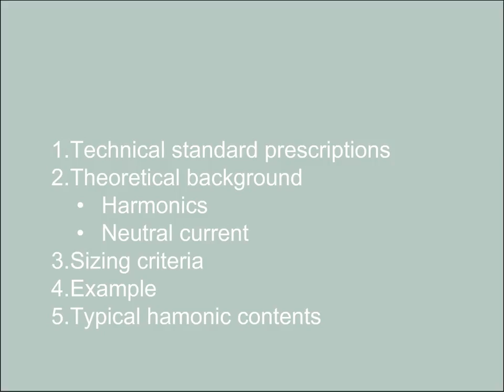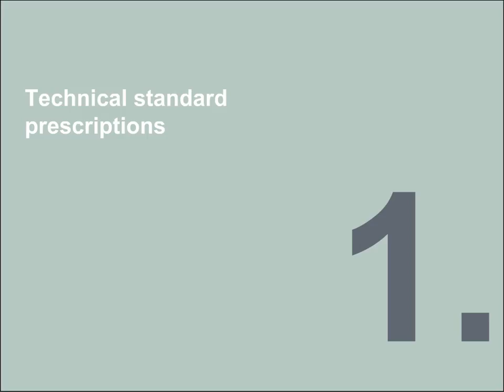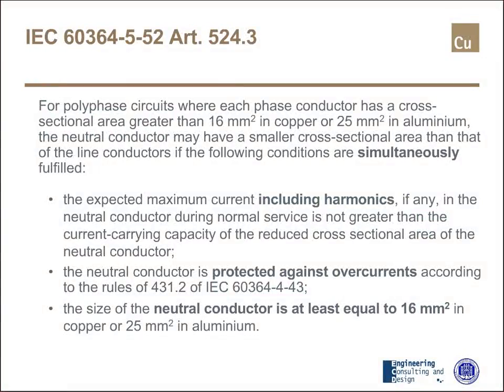Let's start from the technical standard prescription on Neutral Sizing. The reference is the IEC 60364, and specifically Part 5, Article 524.3. This prescription is fully reproduced in the slide now, and I would suggest to read it together. For polyphase circuits where each phase conductor has a cross-sectional area greater than 16 mm² in copper or 25 mm² in aluminum, that is a condition, in this condition...